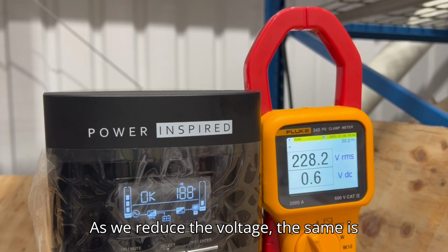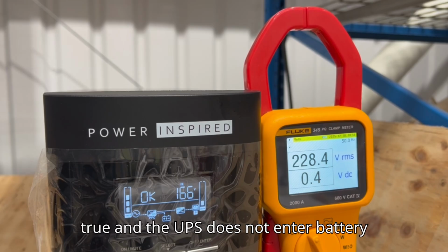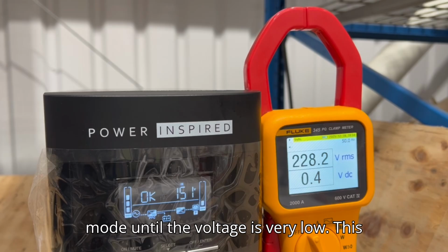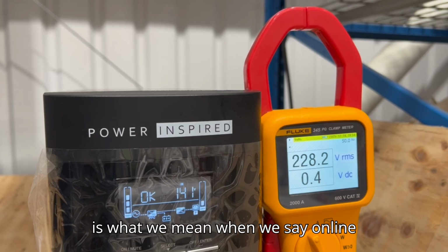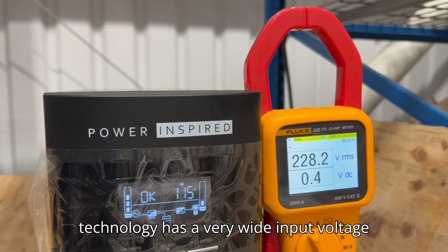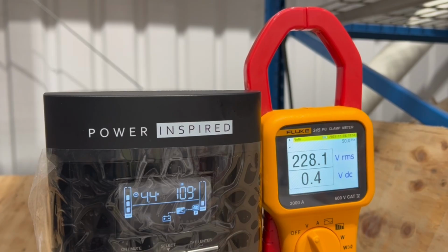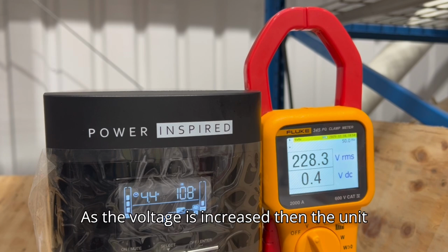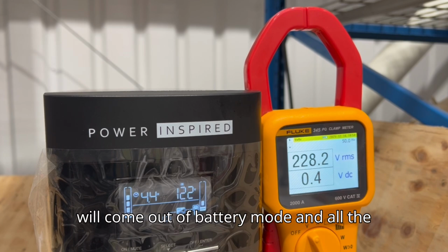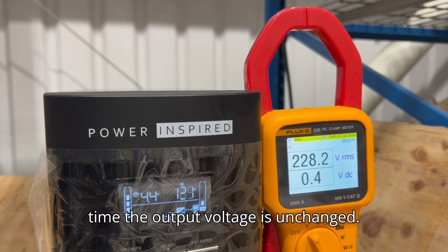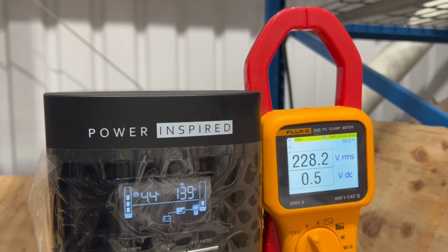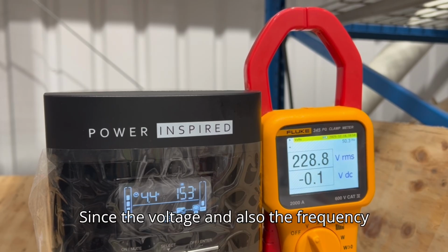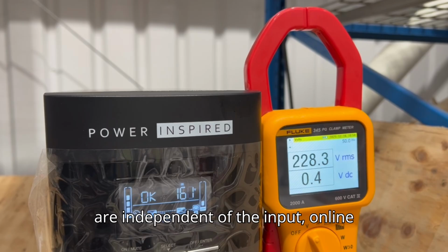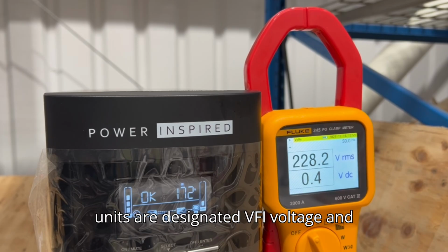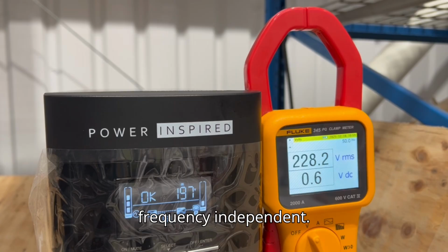As we reduce the voltage, the same is true, and the UPS does not enter battery mode until the voltage is very low. This is what we mean when we say online technology has a very wide input voltage window. As the voltage is increased, then the unit will come out of battery mode and all the time the output voltage is unchanged. Since the voltage, and also the frequency, are independent of the input, online units are designated VFI, voltage and frequency independent.